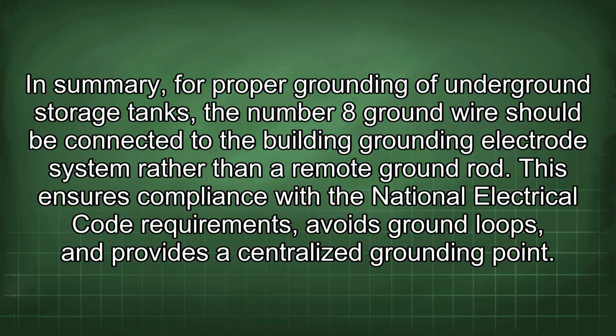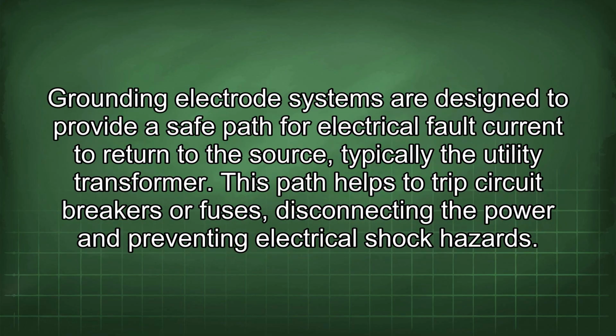In summary, for proper grounding of underground storage tanks, the number 8 ground wire should be connected to the building grounding electrode system rather than a remote ground rod. This ensures compliance with the National Electrical Code requirements, avoids ground loops, and provides a centralized grounding point. Grounding electrode systems are designed to provide a safe path for electrical fault current to return to the source, typically the utility transformer. This path helps to trip circuit breakers or fuses, disconnecting the power and preventing electrical shock hazards.